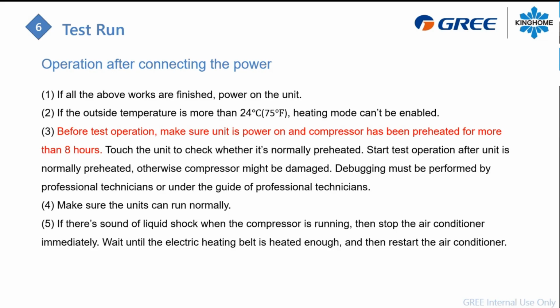So if you touch the shell of the compressor with your hand and you feel it warm, you're good. So make sure to apply the power to engage that heating shell on the compressor to make sure it will be warm enough. Other thing, if the outside temperature is more than 24 degrees Celsius, then you cannot use the heat mode. Okay, so during summertime, heat mode will be disabled if you are over 24 degrees Celsius.